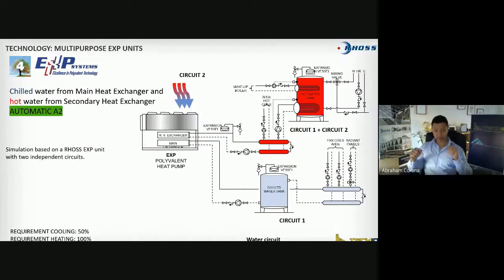By saying that, one circuit is working as a chiller, it is cooling the water in the tank, and all that heat is being used to heat the hot water tank. But if you see, if I only use one circuit, I'm only getting 50% of the demand of the heating.